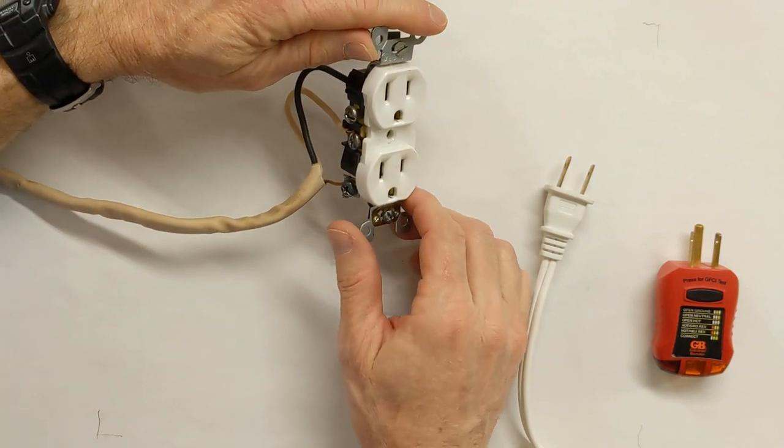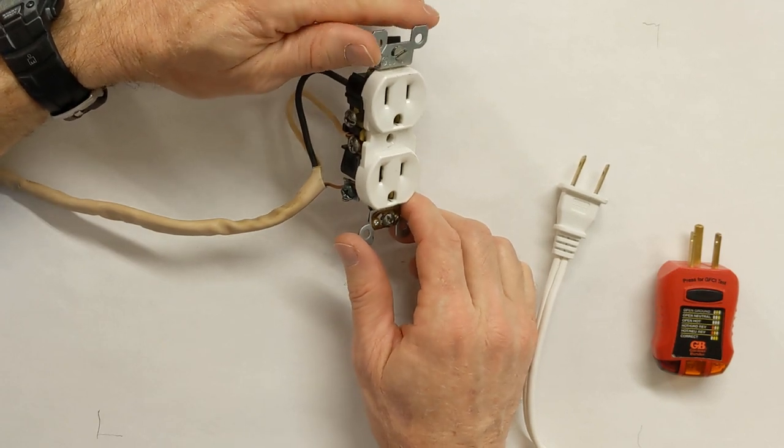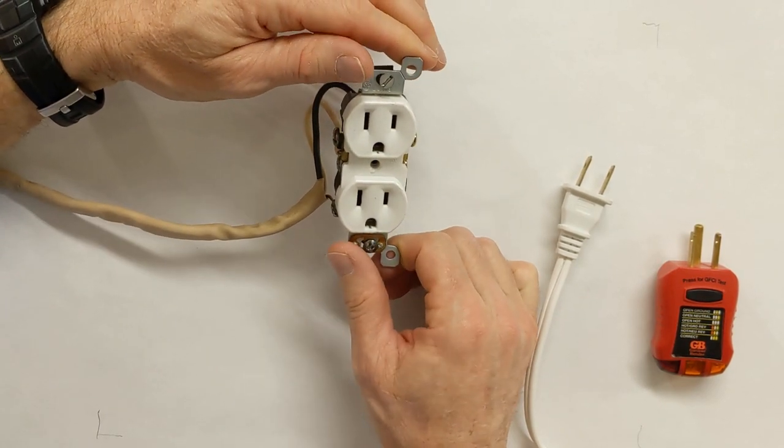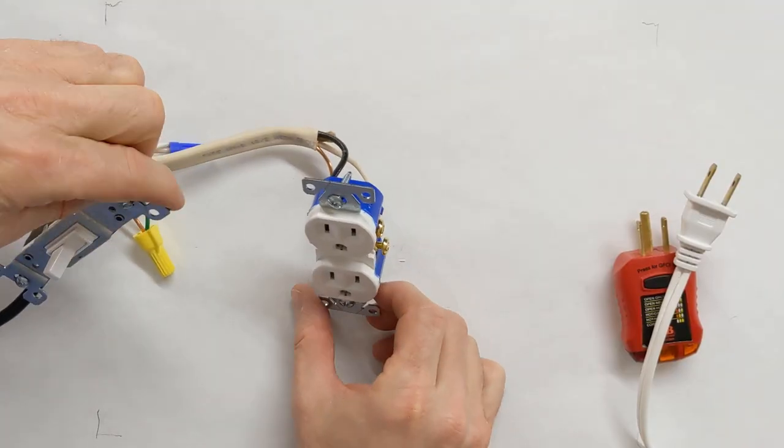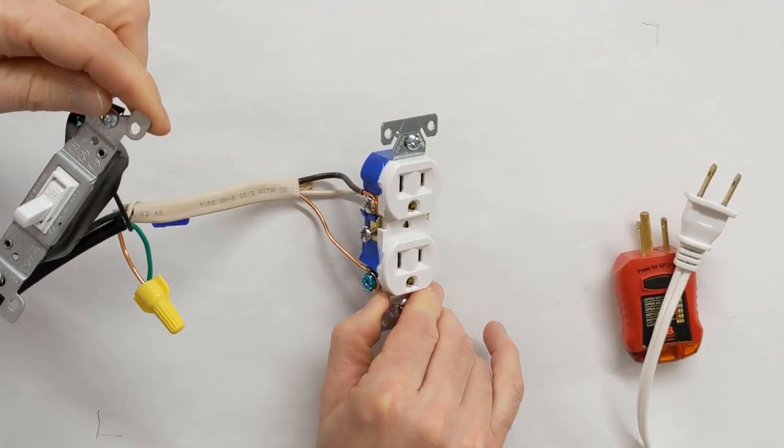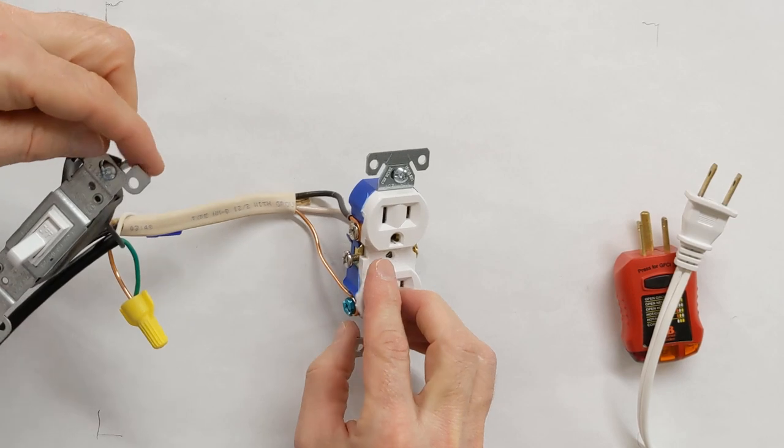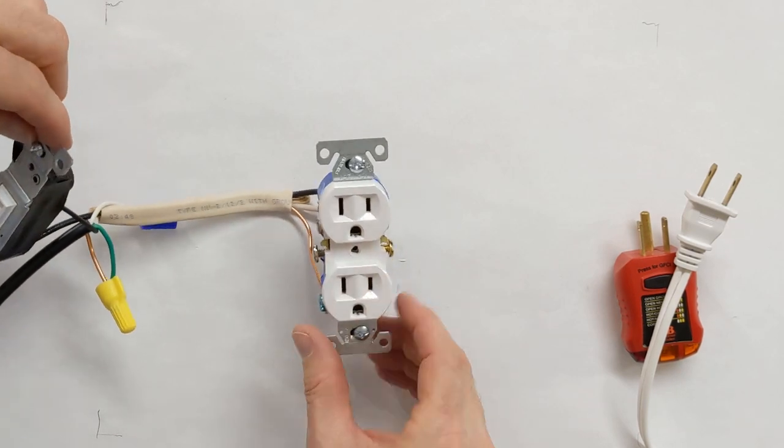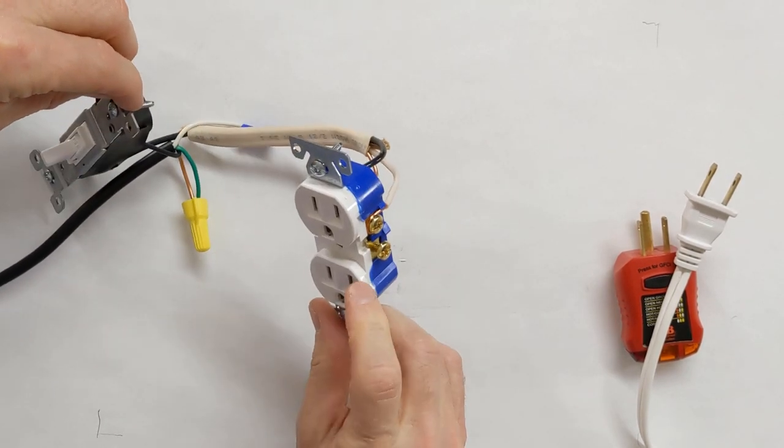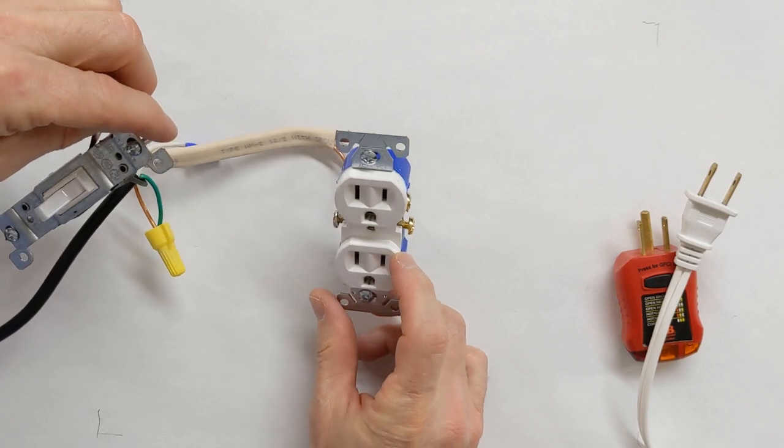If the black and white wires are installed on the wrong sides of the outlet, you get reverse polarity. So this outlet with the black wire on the long slot side and the white wire on the short slot side causes reverse polarity.